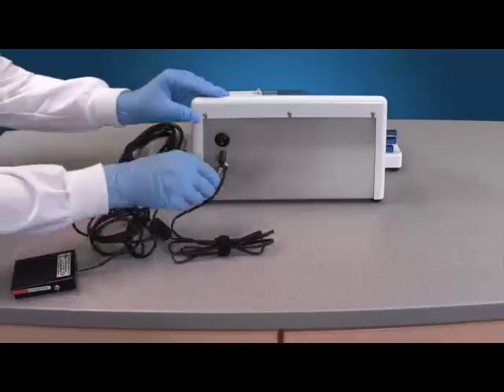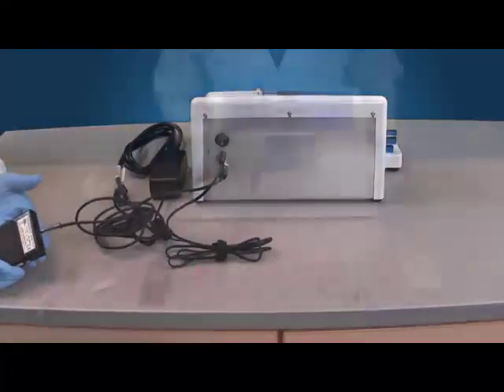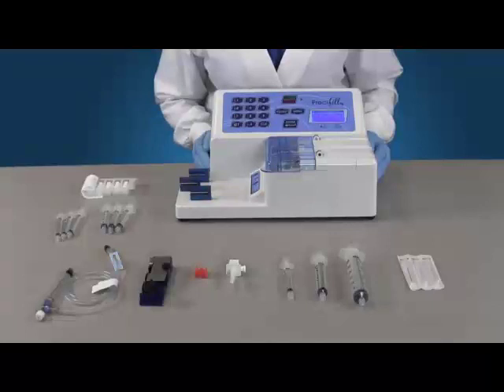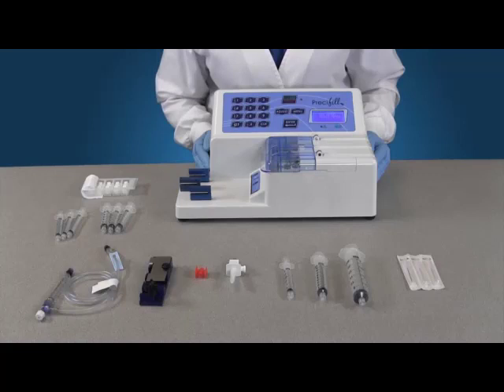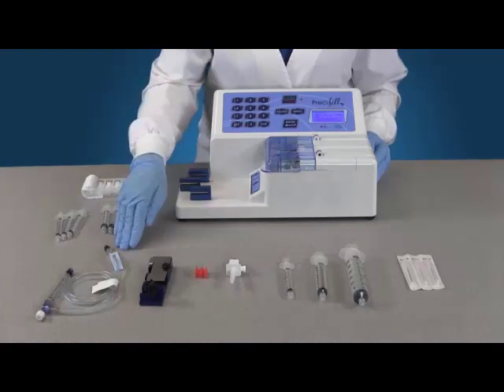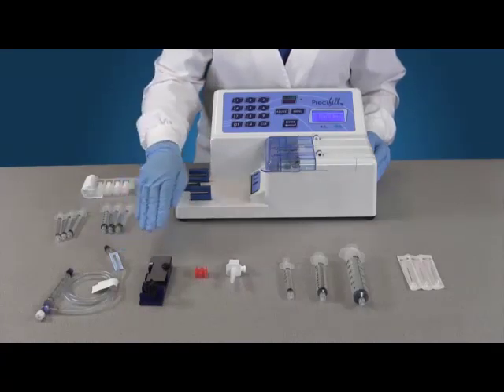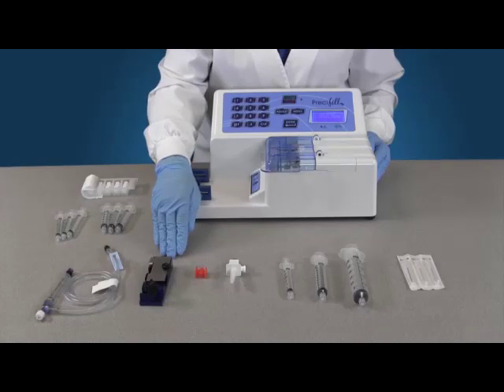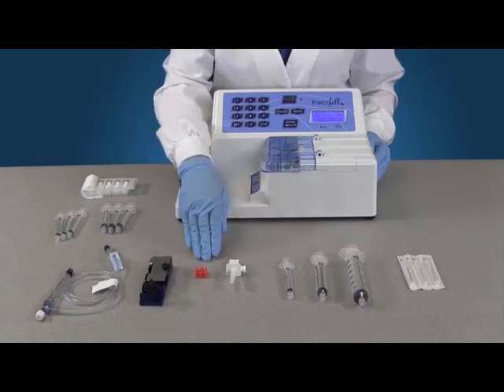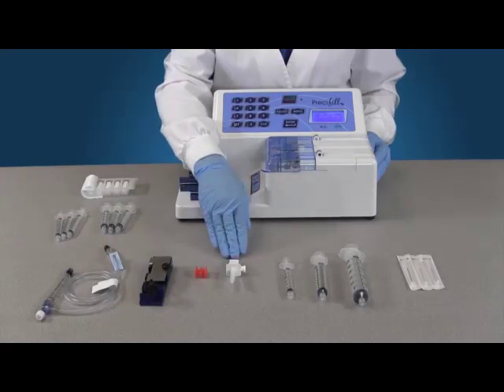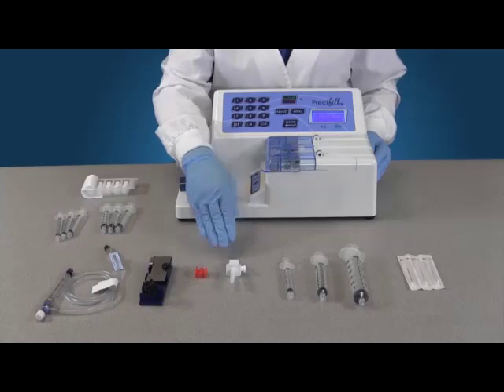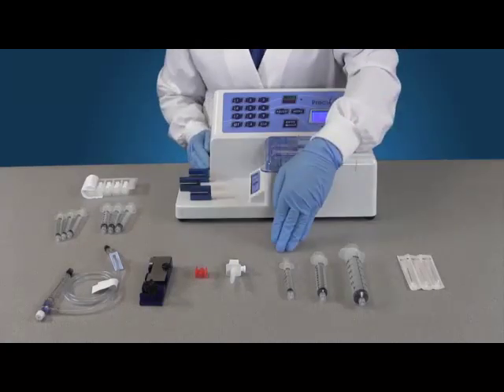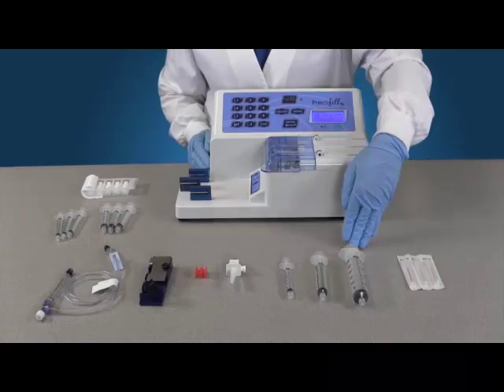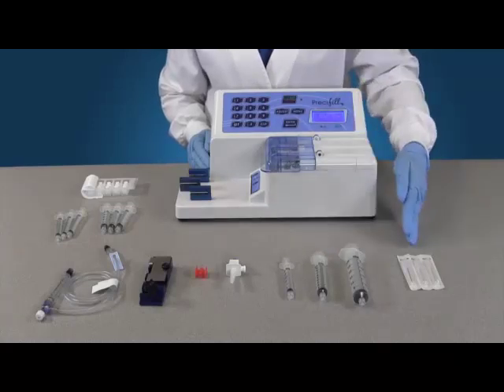Simply plug the foot pedal into the back of the pump and place it on the floor. You are now ready to set up your pump for filling. Before you begin, be sure you have all the necessary materials. For IV syringe filling, you will need a small bore, low-flow tubing set, a block holder that works with both IV and oral syringes, sterile universal syringe tip adapter for IV liquids, connector to liquid source such as a transfer spike, a BD Master IV syringe in 3 ml, 10 ml, or 30 ml, and a needle of choice.